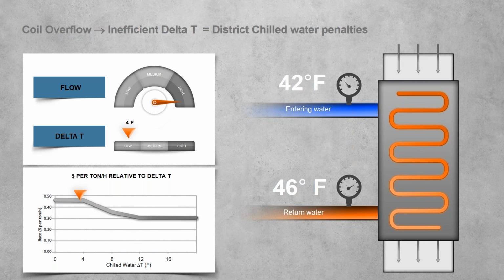When that happened for the state of Tennessee, that decrease in delta T, we could call it, is an inefficient use, and that caused that 12 to 13,000 in the worst case month penalty fee they were paying. This graph on the bottom shows that depending on what the delta T is, the rate that they would pay changes. These are just examples of rates. They're not perfectly specific to the state of Tennessee, but it gives us a nice example of how, when we're not using the chilled water as designed, we get charged a different amount.